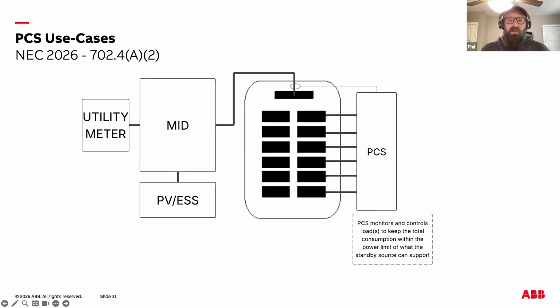When the transfer to the standby source is manual or non-automatic, the code requires the optional standby system to have enough capacity to supply all loads the user intends to operate at the same time. Because the user is making the selection manually, they're permitted to choose which loads will be connected during an outage.